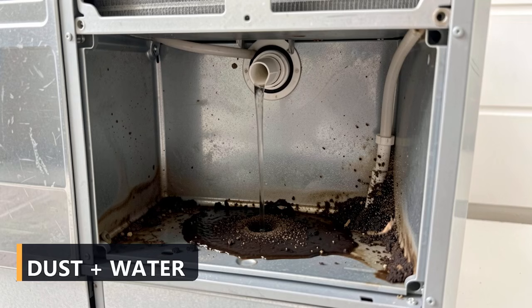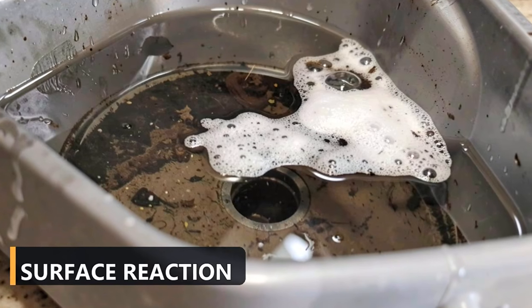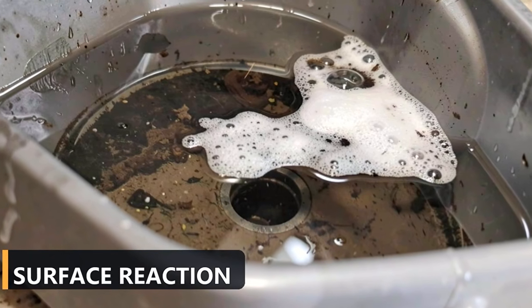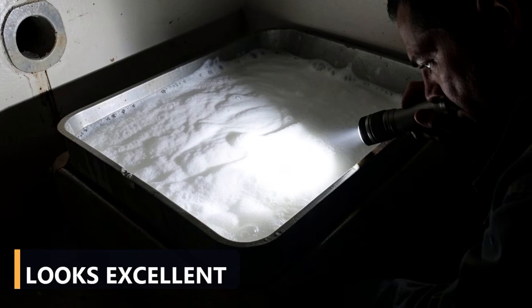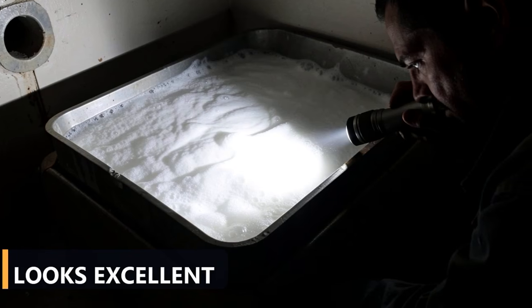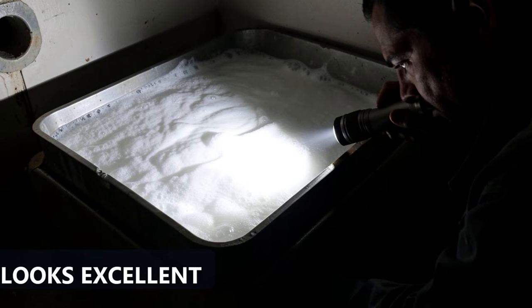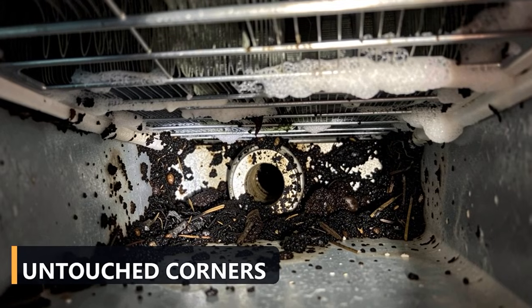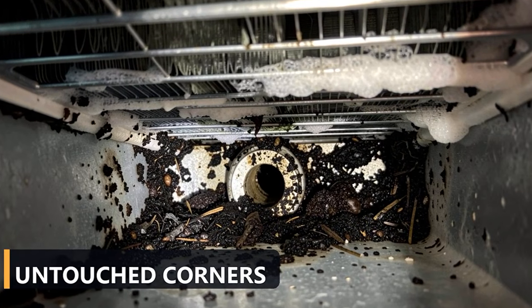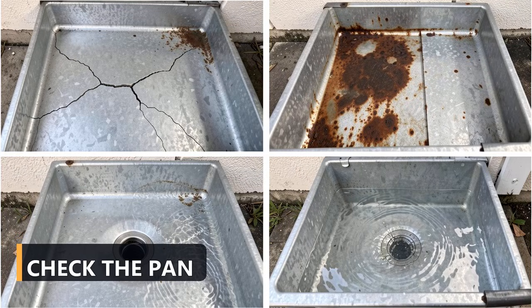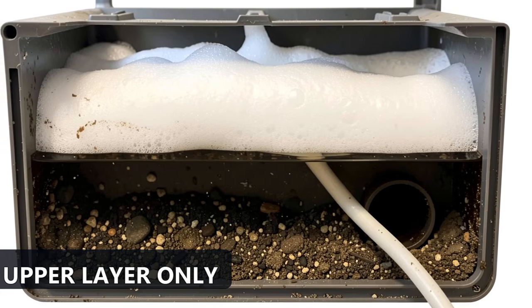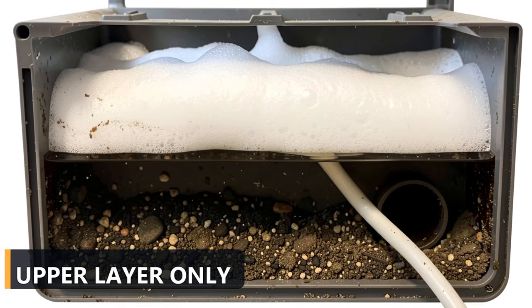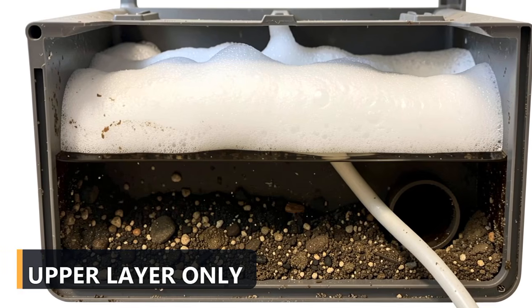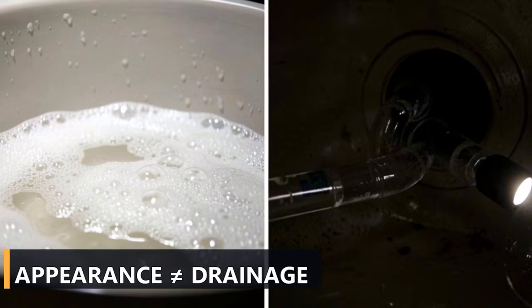Number 5. The drain pan can look clean while the drainage system is still failing. Every cooling cycle pulls moisture from indoor air. Water forms on the cold coil, falls into the condensate pan, and exits through a drain line. Dust that bypasses the filter can mix with this water and create dark sludge. That damp reservoir can support odor and microbial growth, especially if the pan holds standing water. When peroxide lands in the pan, it may foam through the upper layer and loosen some residue. The immediate result looks excellent.